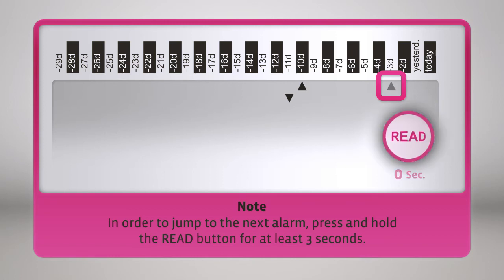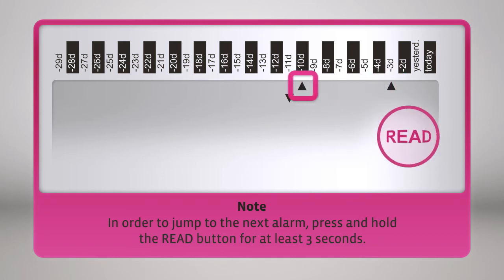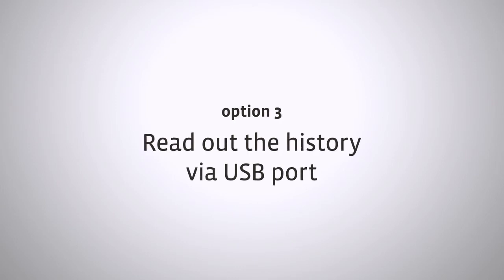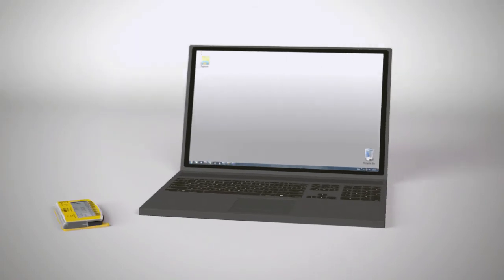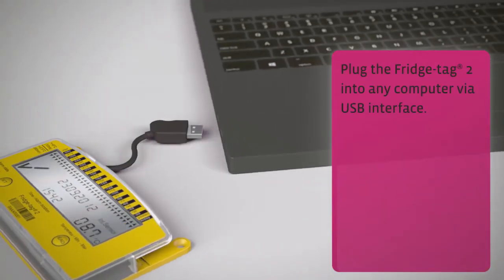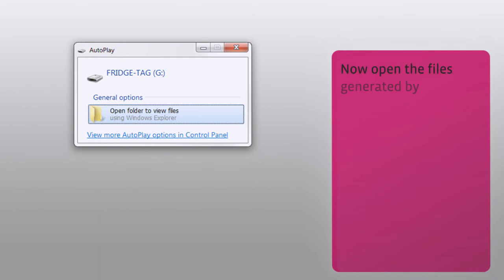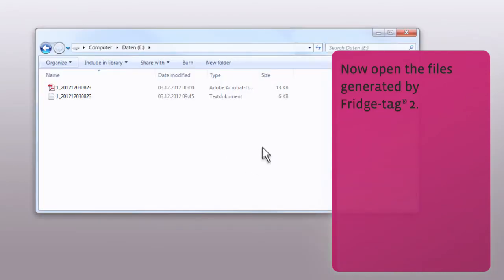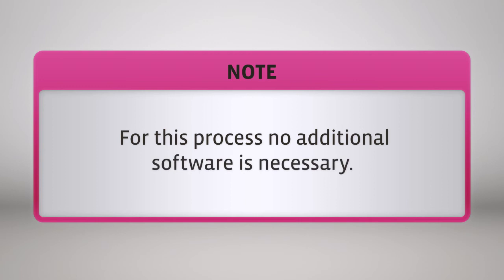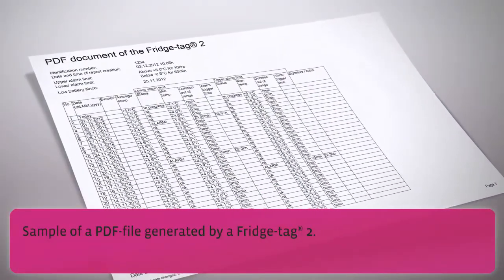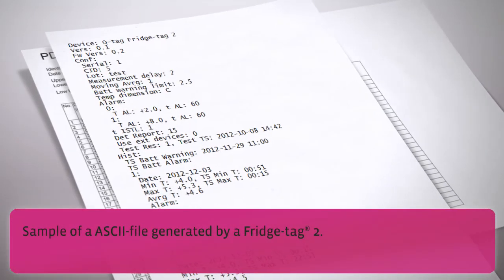In order to jump to the next alarm, press and hold the read button again for at least 3 seconds. Third option: how to read the history via USB port. Plug the Fridge Tag 2 into any computer via USB interface. The following window will appear. Now open the files generated by Fridge Tag 2. No additional software is necessary. A sample PDF file and a sample ASCII file can be generated by the Fridge Tag 2.